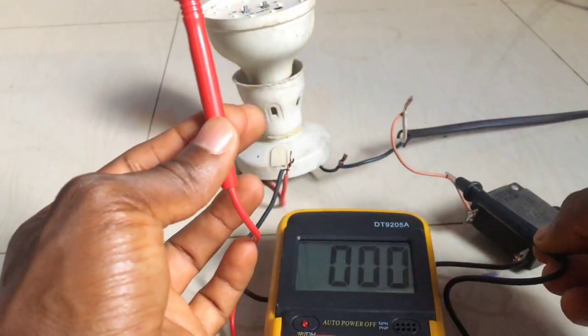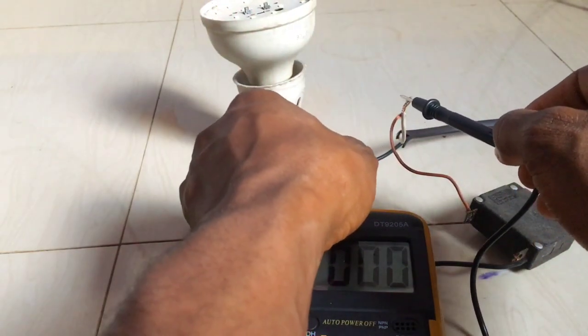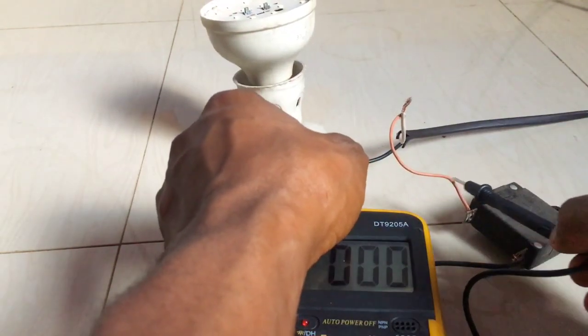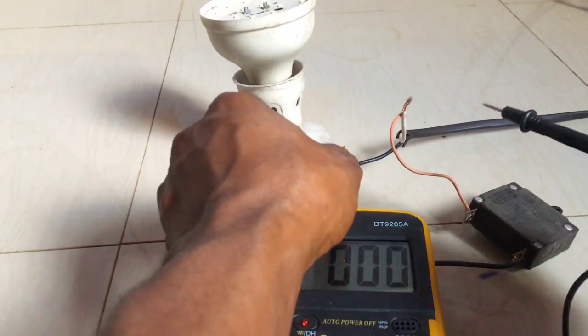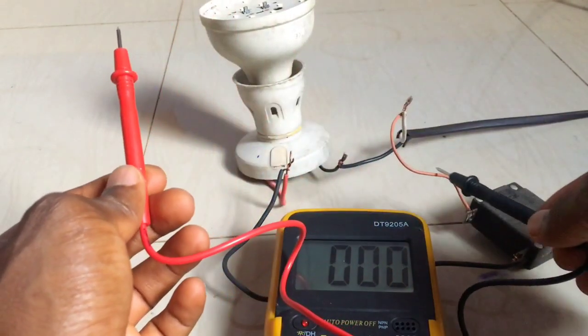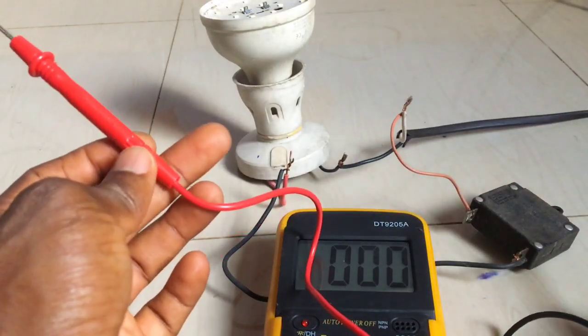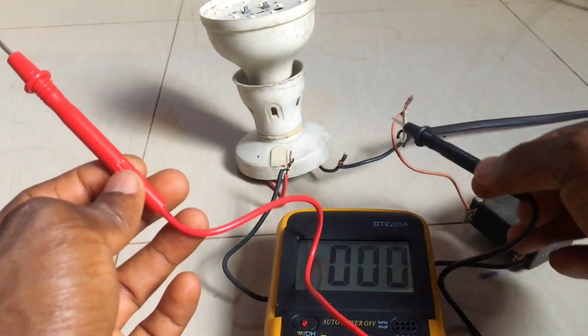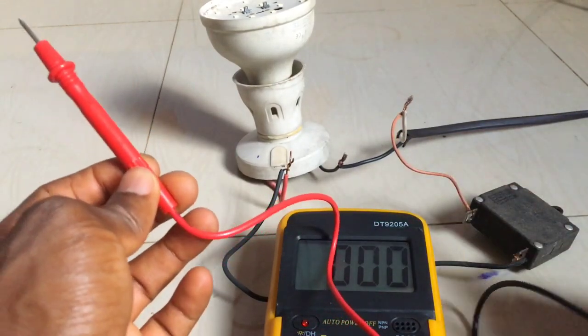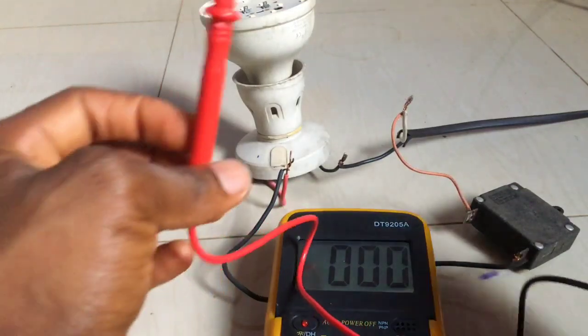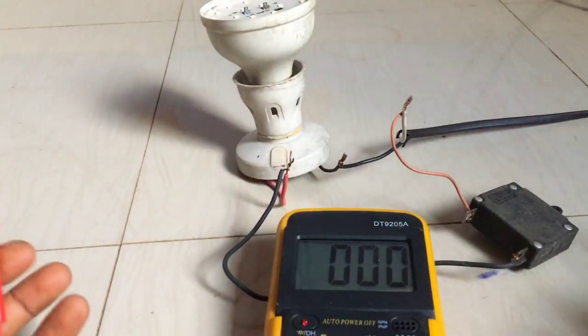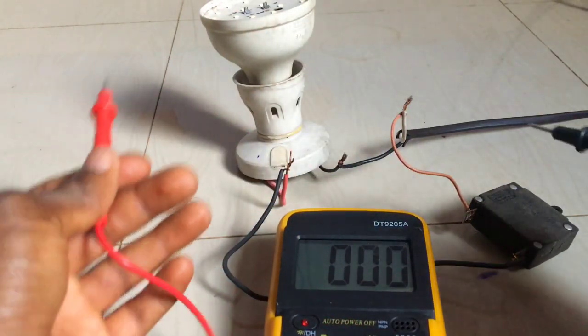But if you don't get voltage between this hot line from the breaker and a neutral point, then you know that you have to trace to the distribution board, the circuit breaker supplying this cable from the distribution board. You have to rectify it if it is not in order. So this is just how to go about troubleshooting issues concerning your lighting point.